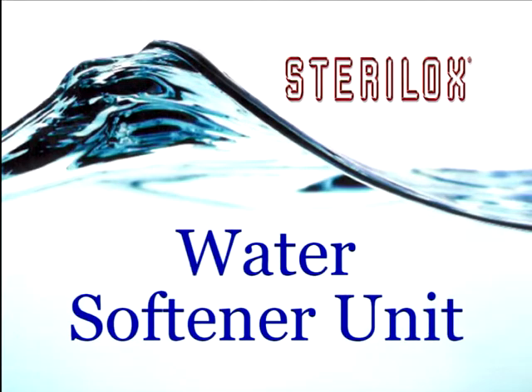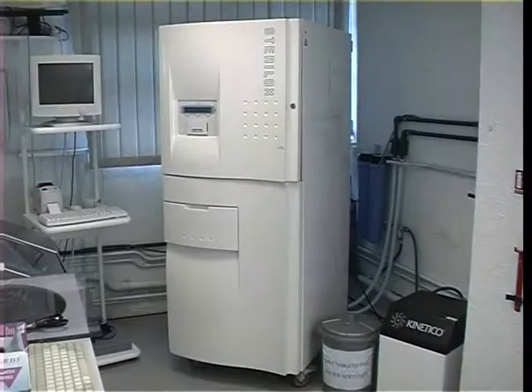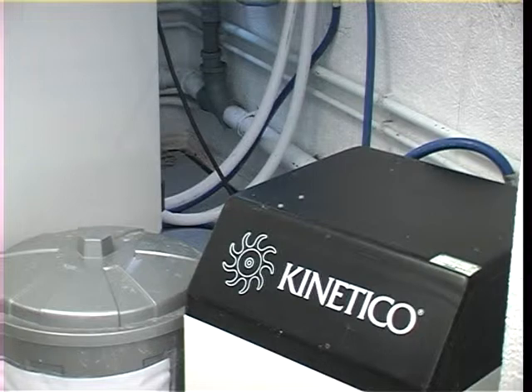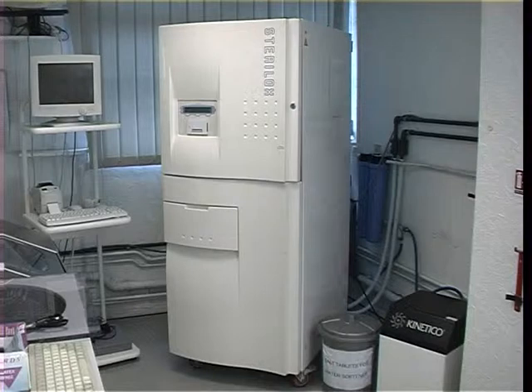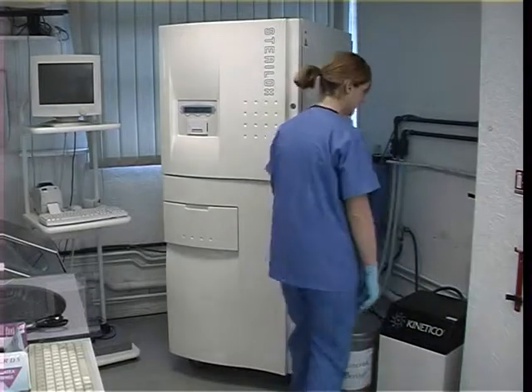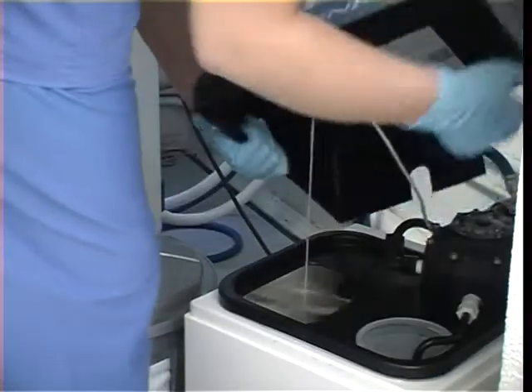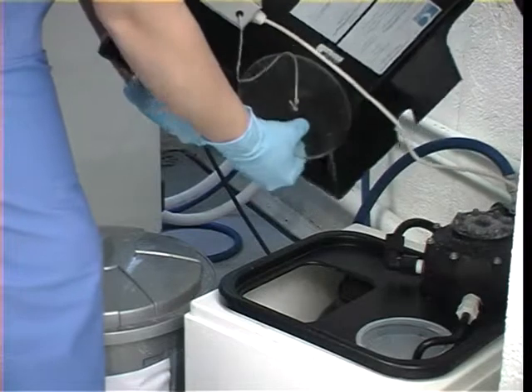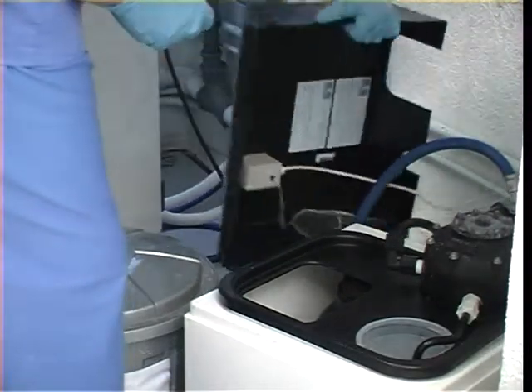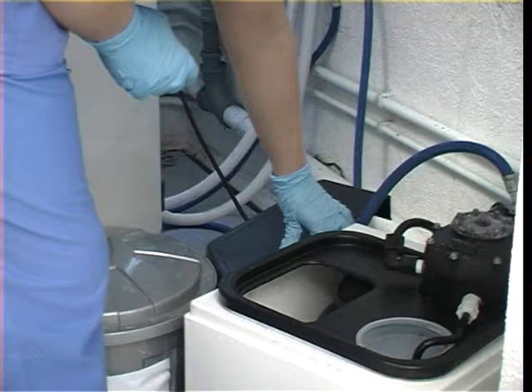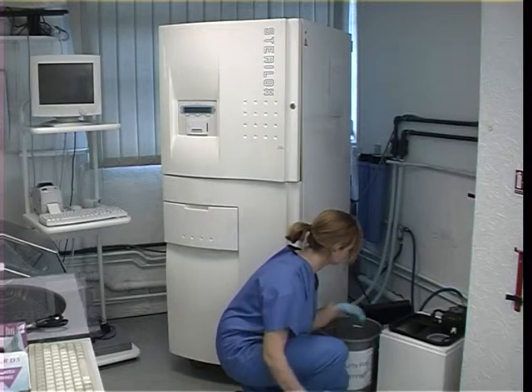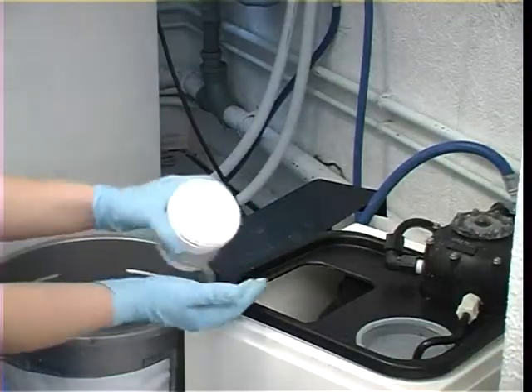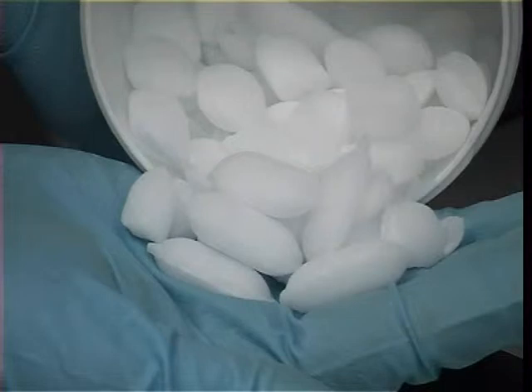Water softener unit. The water softener is an essential prerequisite for Sterilox production and is used in conjunction with the Sterilox generators. The salt level in the water softener should be checked daily and salt added when necessary. When removing the lid of the water softener, you will see this round plastic disc attached to the lid. This is the salt level alarm. If your salt level does become too low, the unit will give out an audible alarm to alert you to add salt. However, this alarm is specific to this type of water softener and may differ depending on the model you have.